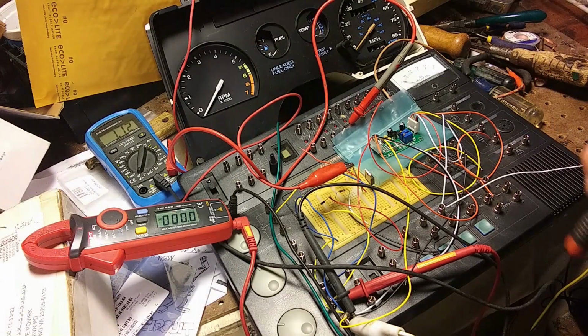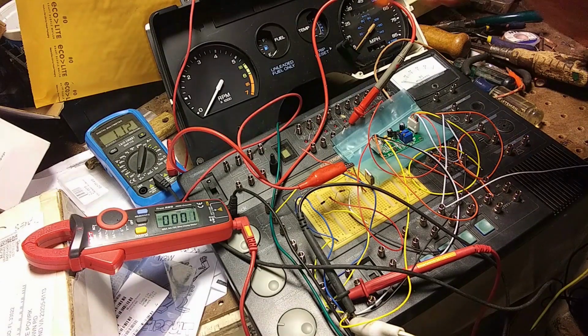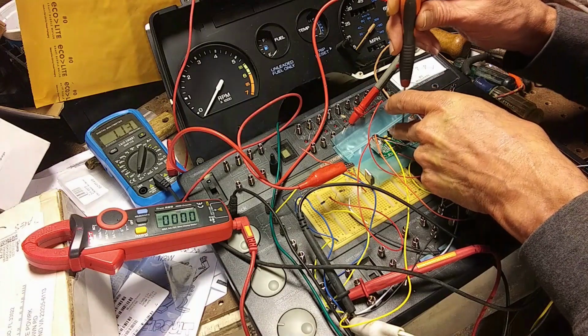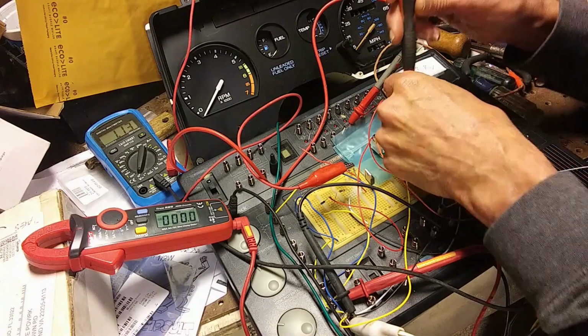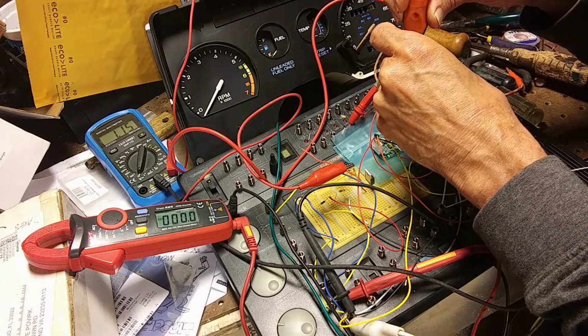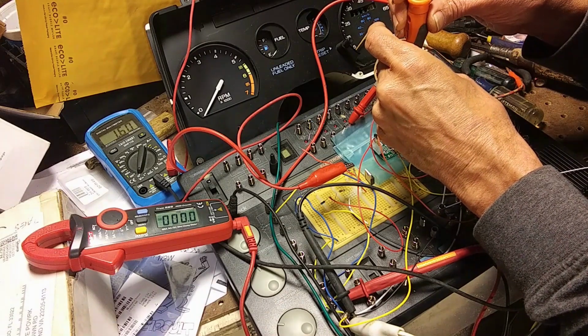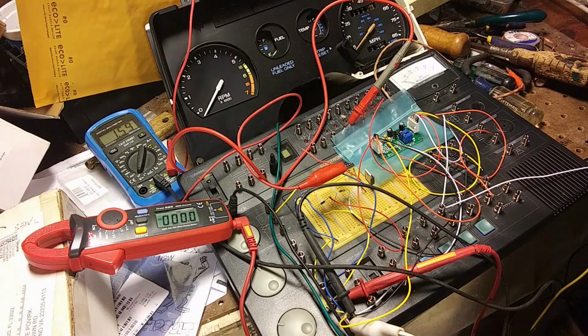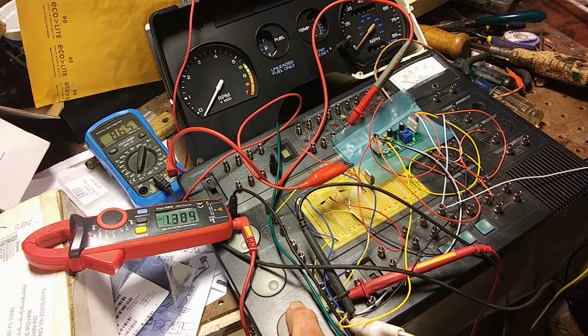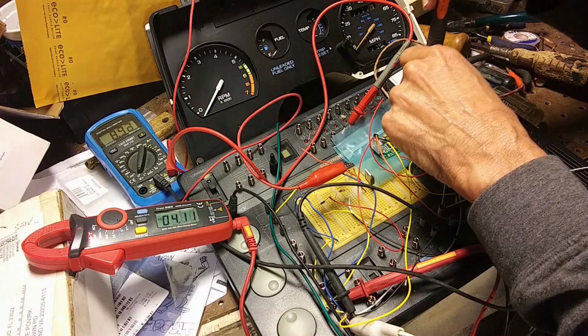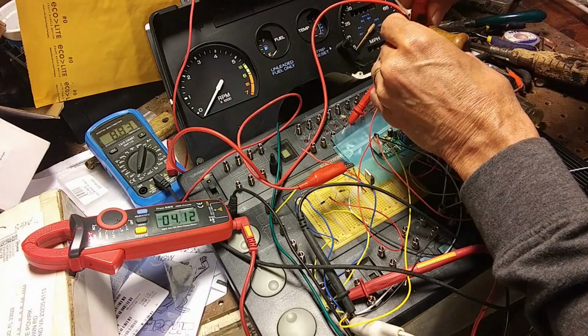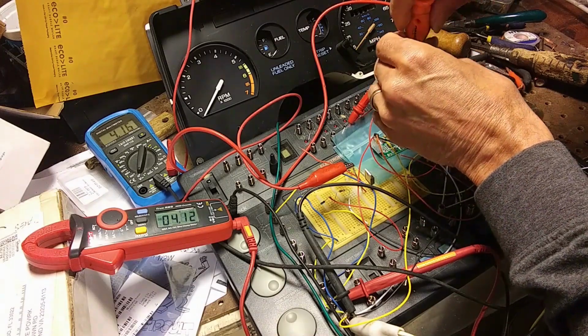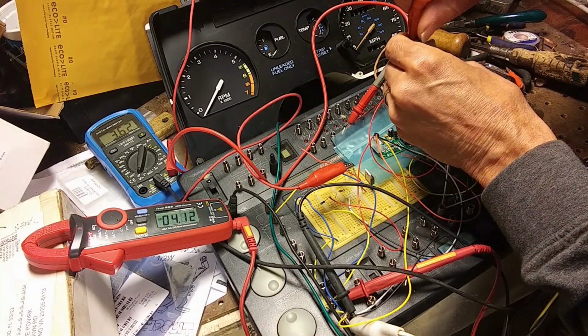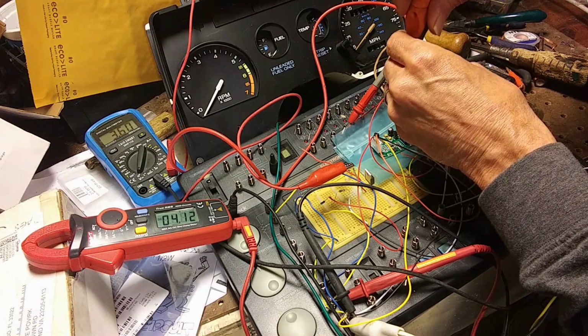So it reads 1.12, and when that's 0 we want this to be 1.6 - this is the 0 adjust. Okay, 1.6. Then when we turn this to 4.1, we want this to be 3.6, so that means adjusting the gain. Okay, 3.6.